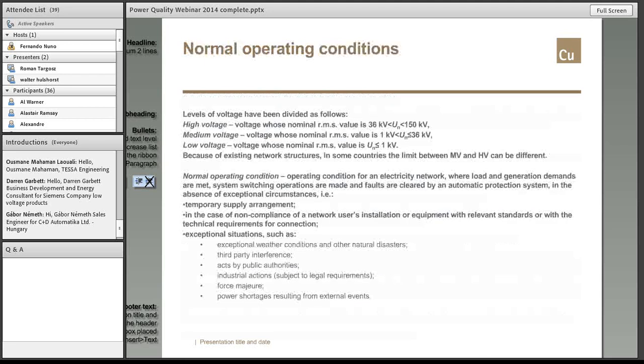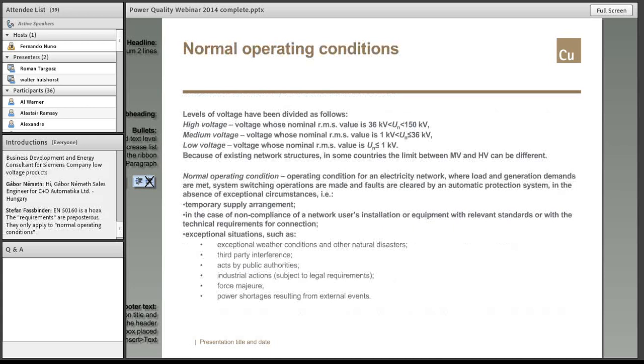Then we've got the definition of what is normal operating condition, and then EN 50160 divides voltage into three voltage levels. One is high voltage, which is between 36 kV and 150 kV. We don't have extra high voltage because customers are not connected to extra high voltage terminals. We've got medium voltage between 1 kilovolt and 36 kilovolt, and low voltage with RMS value below 1 kilovolt. In some countries there is a provision that some borders, some limits, can be slightly different.